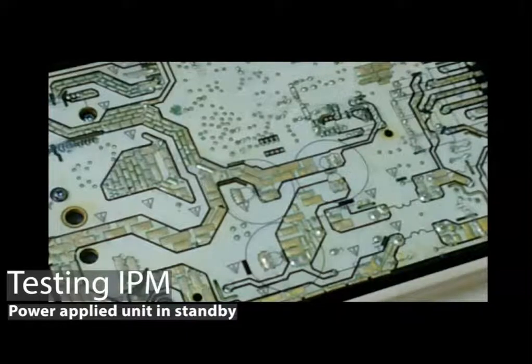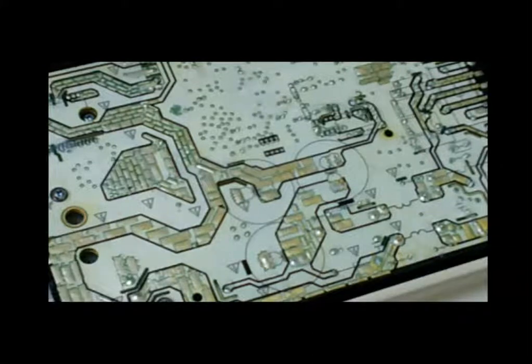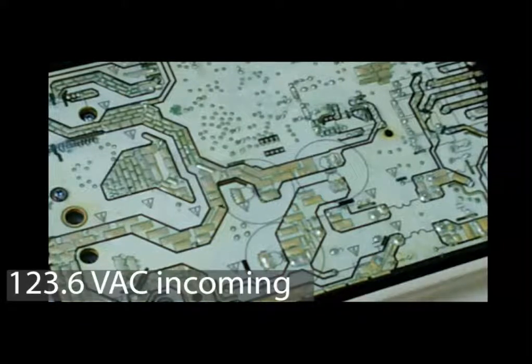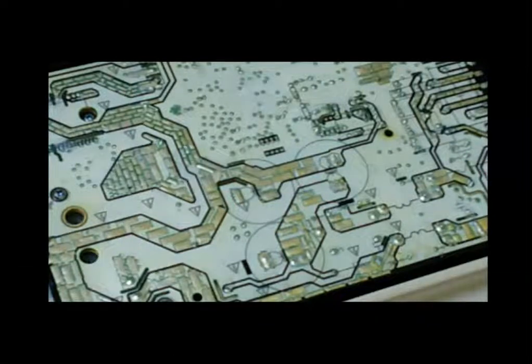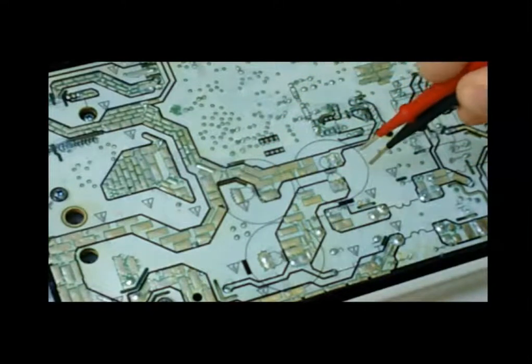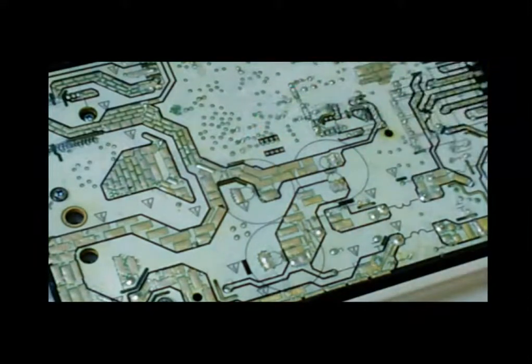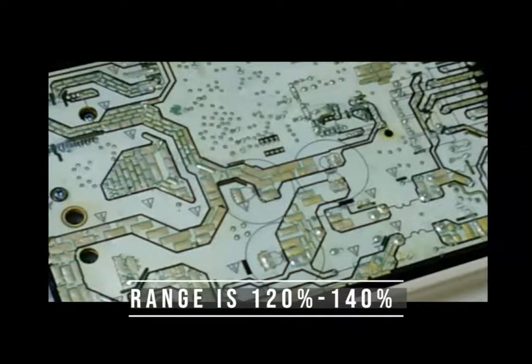All right, so we're going to check the capacitors. That's going to give us our IPM check. So what are we going to be looking for? Well, once again, we're going to take the incoming voltage, and we noted that voltage to be 123-ish. We're going to test the capacitors. Now, what's nice about testing the capacitors is they're marked. Right on the other side of this circle is that capacitor itself. Now, we're going to have super high direct voltage, so that's DC voltage, and we're going to be at 1.4 of the value of incoming as our goal.